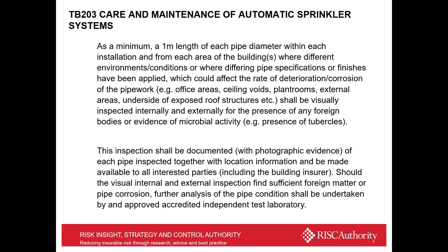You shall then photograph the evidence of each pipe inspected, confirm the location of it, and write a report. That is the requirement of the standard, that a report is written on the condition of the pipework internally and externally. Should there be any further findings or any foreign matter or pipe corrosion, then it can be sent away for further analysis at an independent test laboratory. So that is the new requirement that supplements Annex K and has been rewritten into TB203.